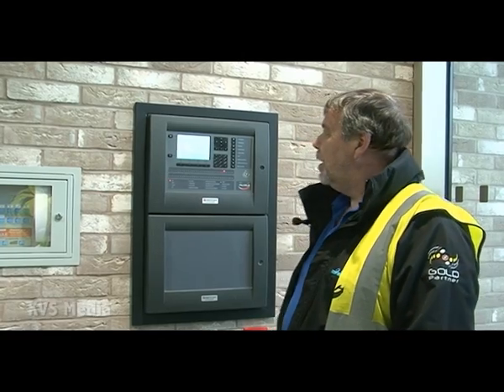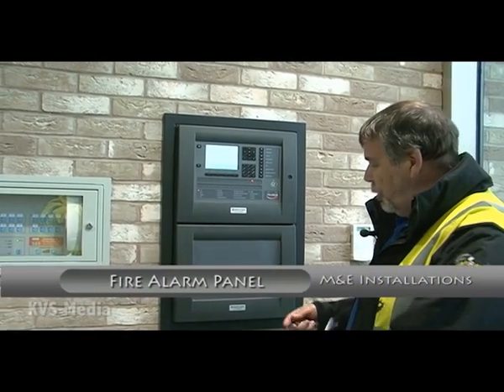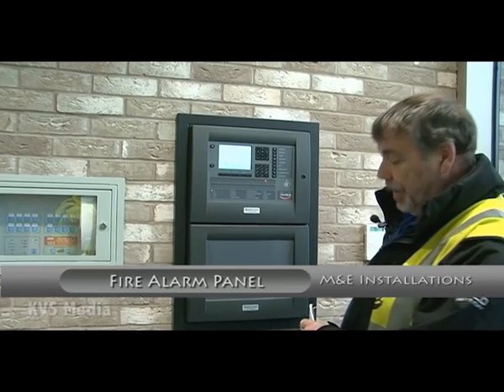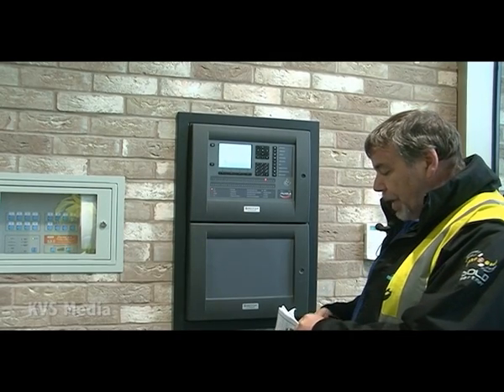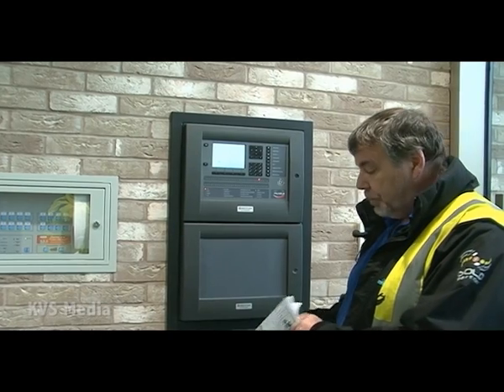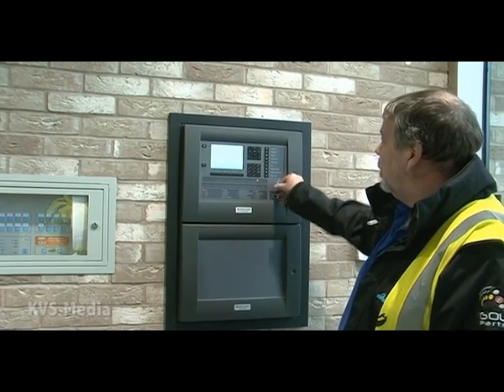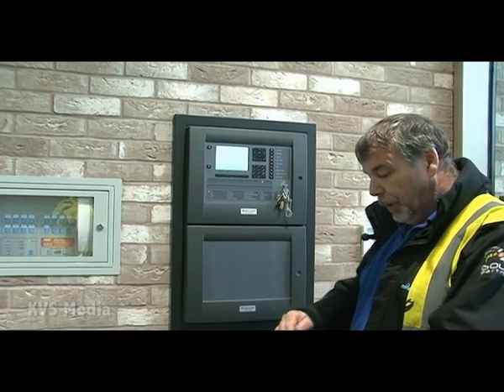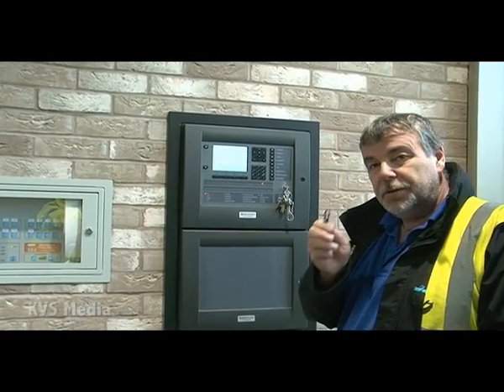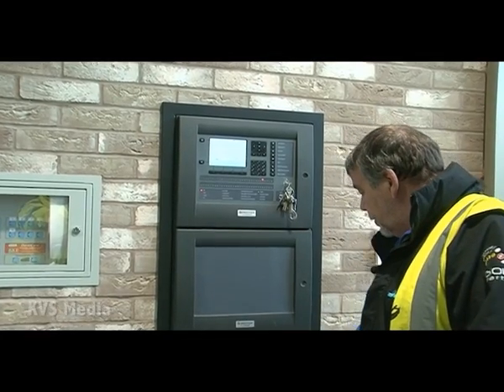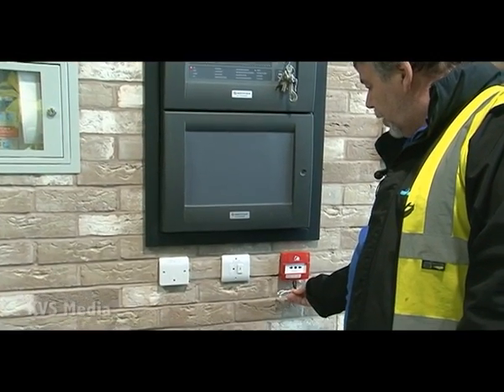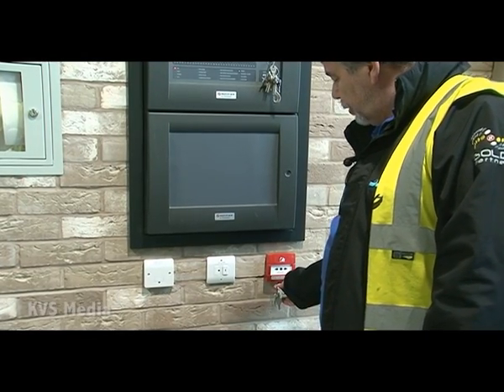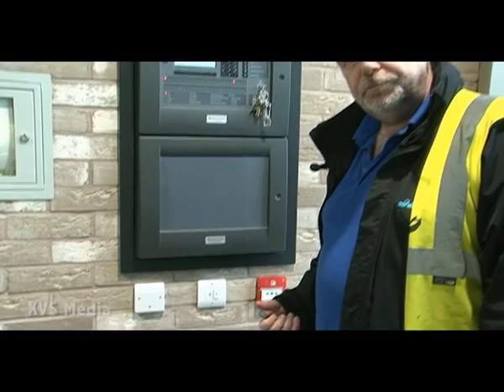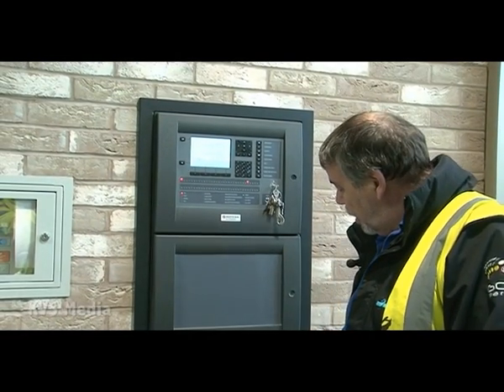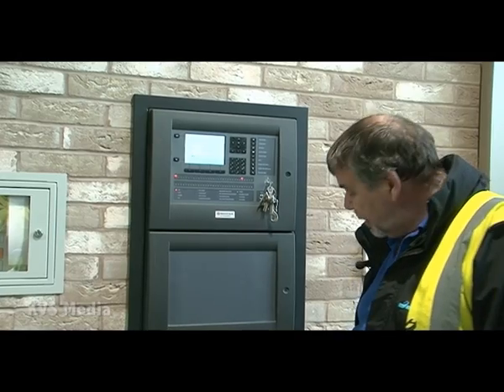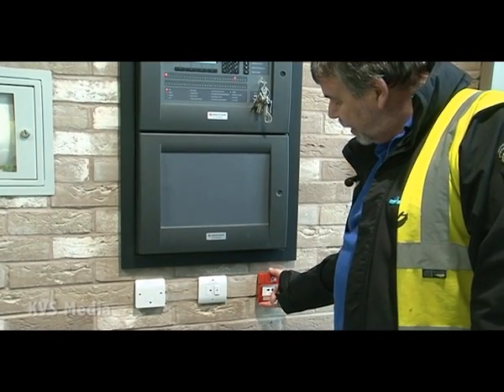So what we're going to do is, with the system in normal mode, which unfortunately it isn't at the moment, I'm going to put a controls activate key in the panel to enable the push buttons and turn that to the right. And for a weekly test, you utilise this shape key, insert to the middle of the break glass at the bottom until it clicks, and then pull the key out, generating a fire condition. And having got the fire condition to register, you then snap the break glass shut again by squeezing it top and bottom.